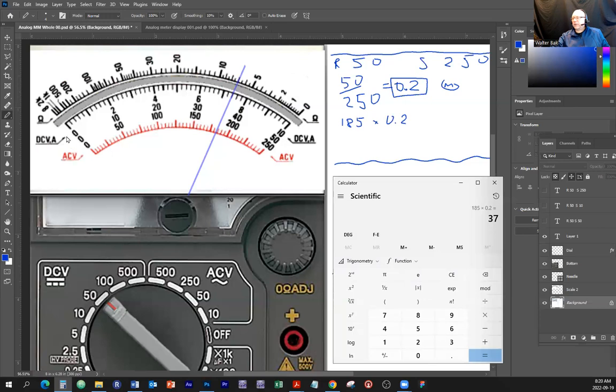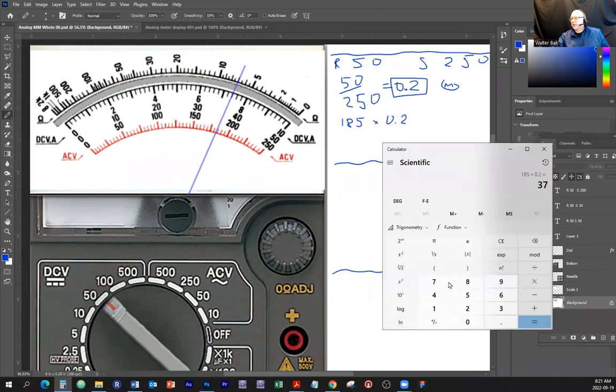All right, so what is the reading that we get on the scale of 0 to 10? Let's see, counting the divisions: 2, 4, 6, 8, 10... that's 7.4. So the reading is 7.4, and the multiplier is 5, so 7.4 times 5 gives us the final reading.